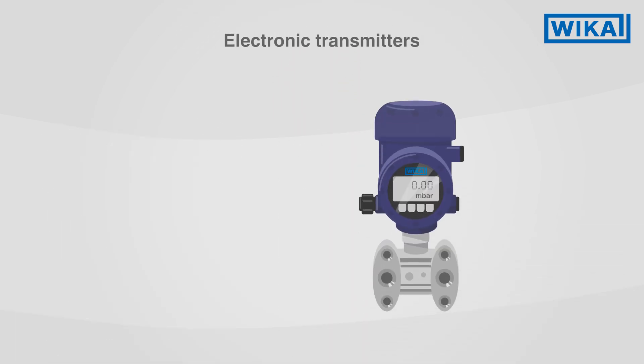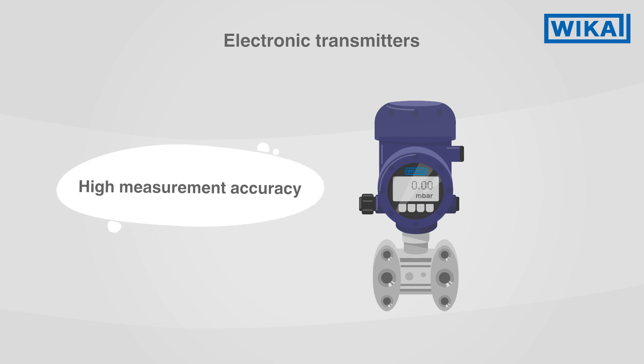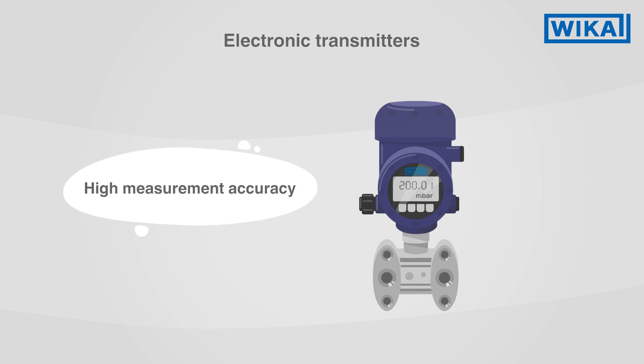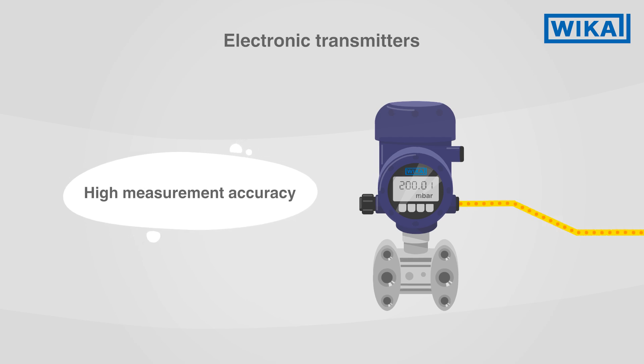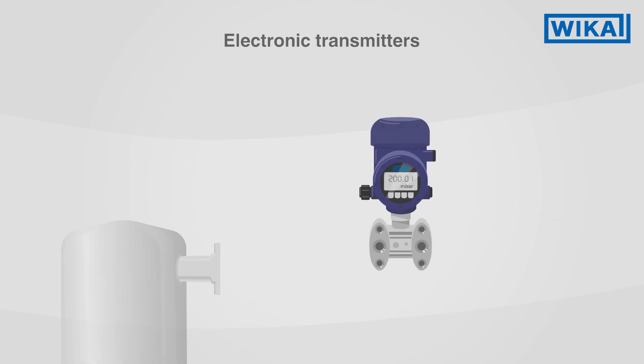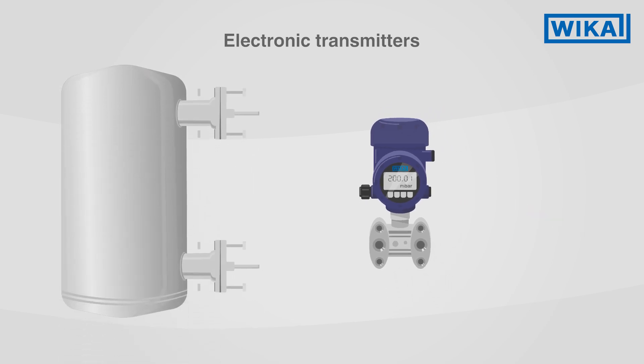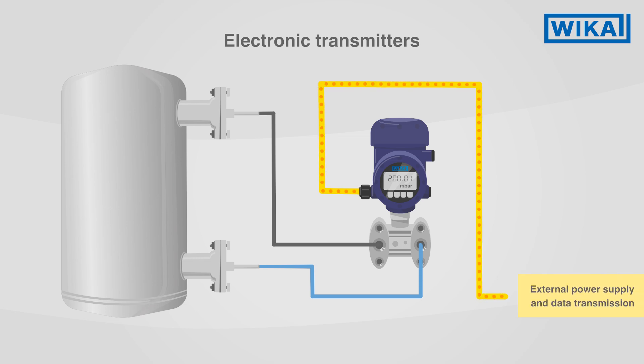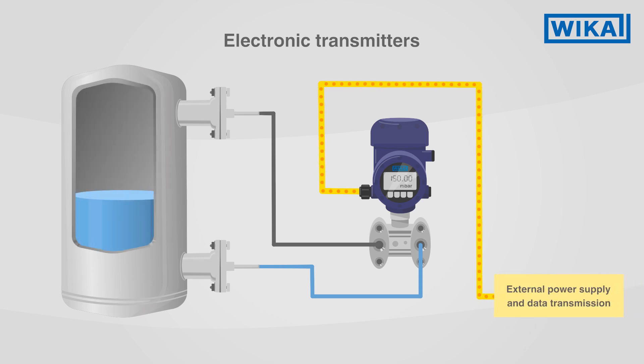Electronic transmitters are used when measurements need to be taken with particularly high accuracy and the measured data not only needs to be displayed but also transmitted. They are used, for example, to detect the level in closed vessels with liquefied gases.